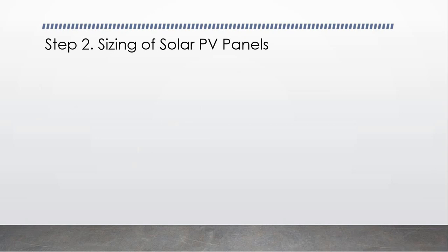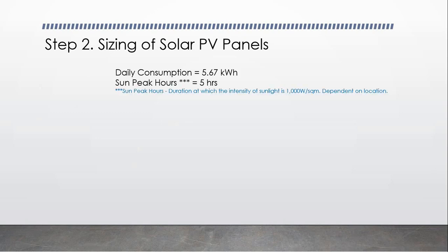Step two is the sizing of the solar PV panels. Now that we have calculated our daily power consumption, we also need to determine how much sun your location gets, or what we call sun peak hours. The sun peak hours is the duration at which the intensity of sunlight is 1,000 watts per square meter. The average is usually around four to five hours, and that value varies as you move away from the equator. There are locations with longer days and some with longer nights, so you need to look this up. You can use four or five hours if you just want to approximate.